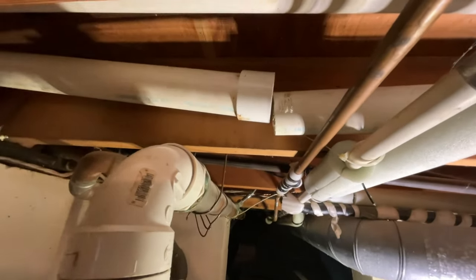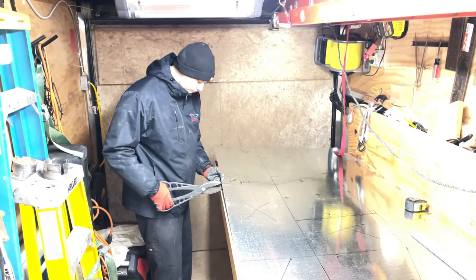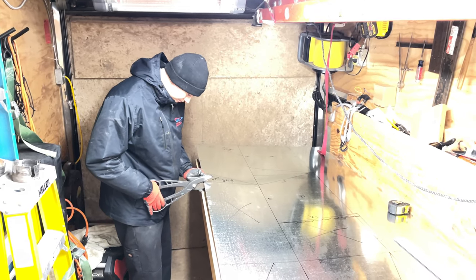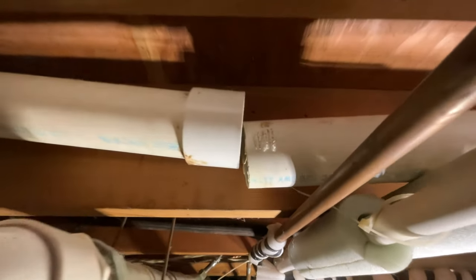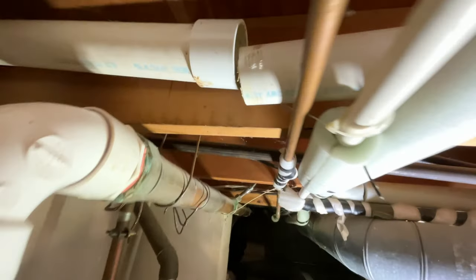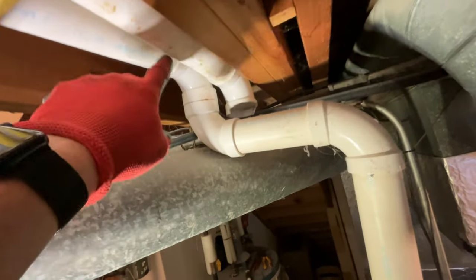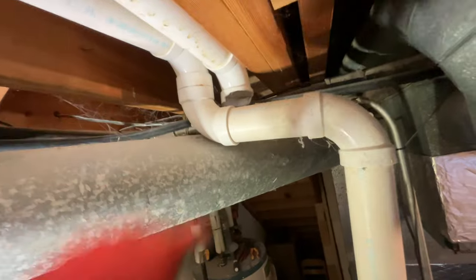I have updates. Tyler's out there building metal. This is the old exhaust — it's not even primed or glued. How is that even going to seal? It looks like they cut it with a saw and didn't even finish it, and it's been like that for 30 years. I'm going to take this piece off and put a new piece on, because I've got to use some long sweep radius 90s anyway.